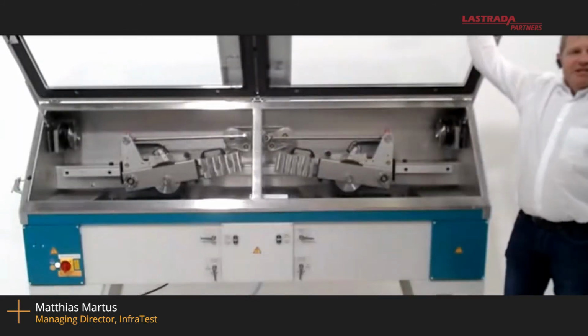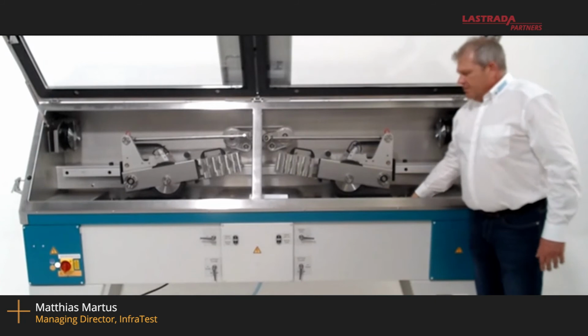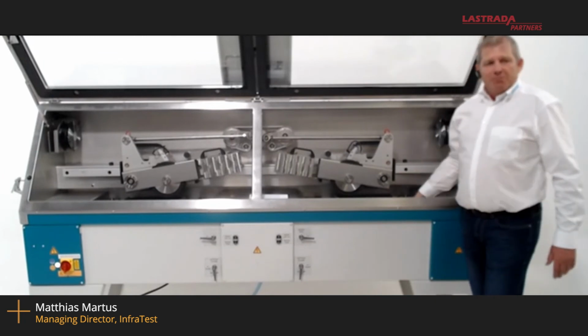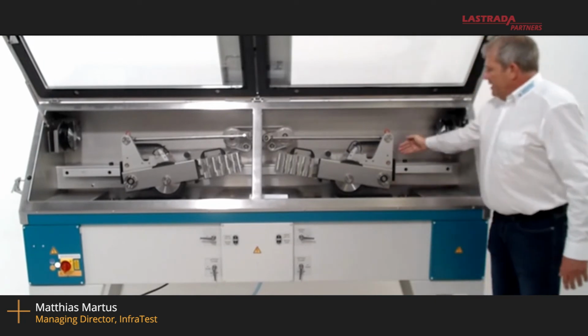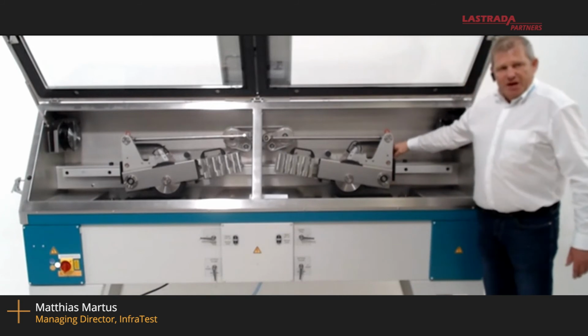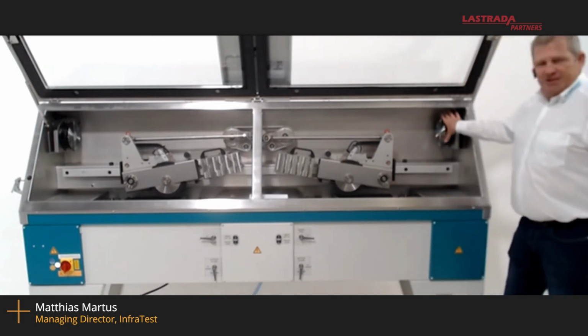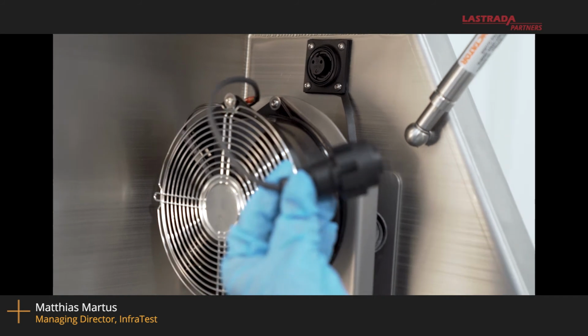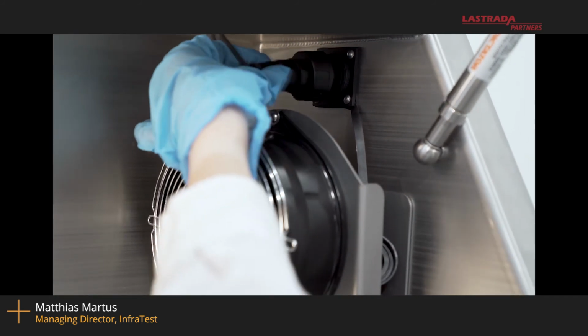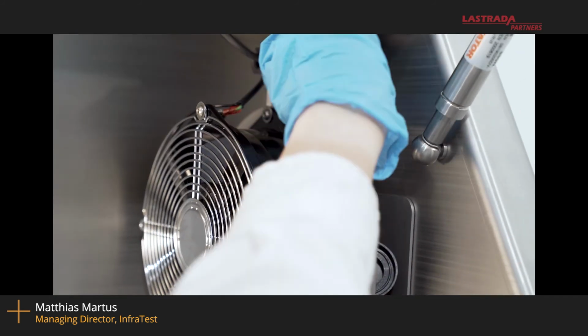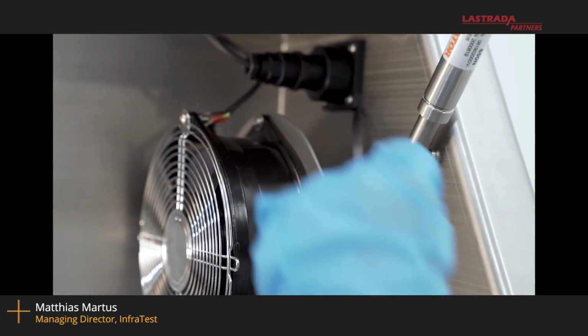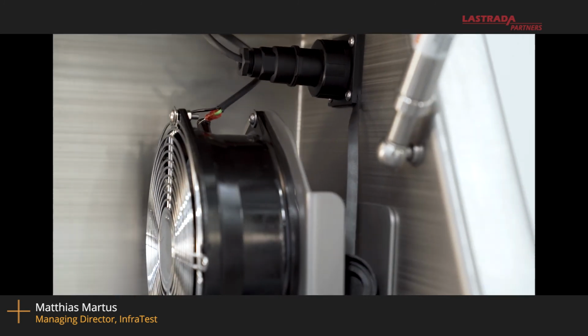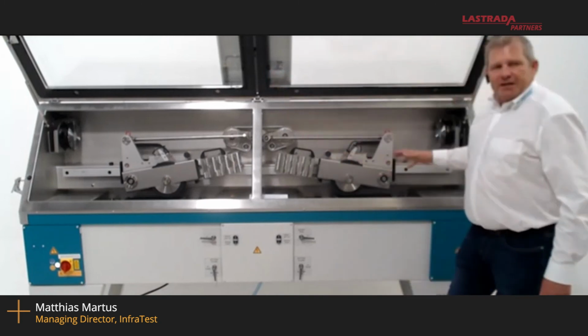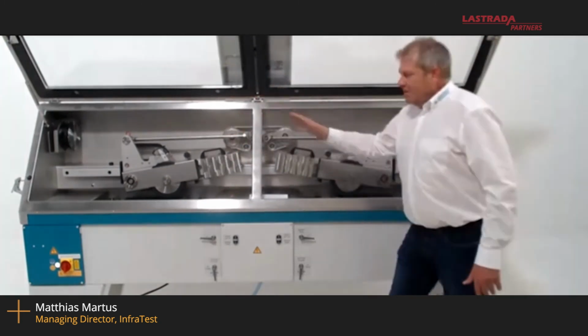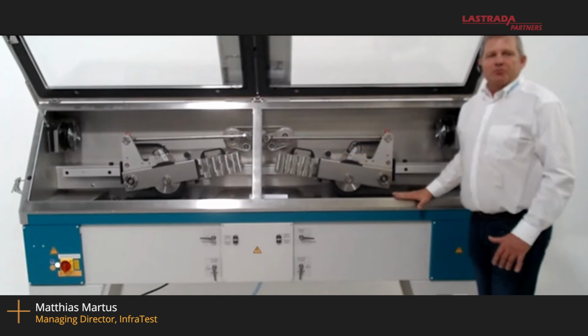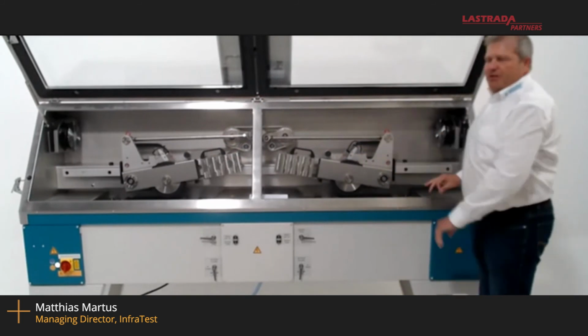We have 3 heating systems inside the machine. One is in the base, underneath the sample, which is the water heating system. Behind here in this frame is the heating system for the air, and the ventilation system on the right side and on the left side is moving the air in certain circles. We normally test it: we put some smoke inside and start the machine, and we see that it's running like an 8-shaped wind inside the machine, in order to perform a constant temperature within the complete chamber.